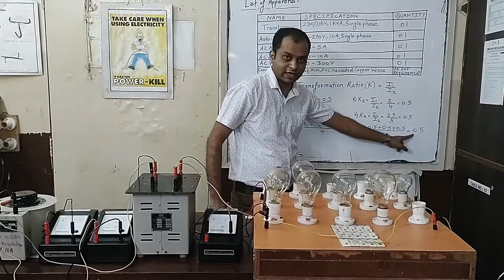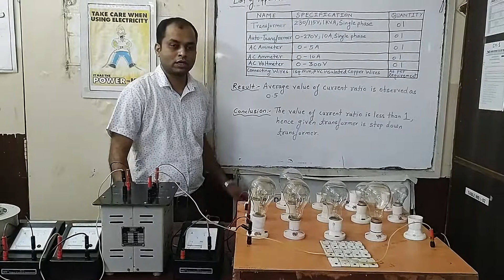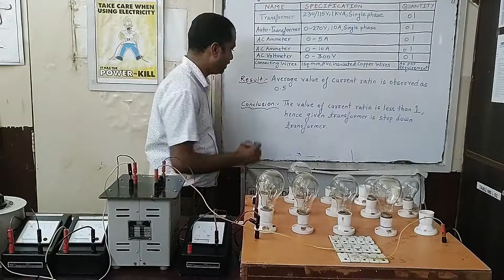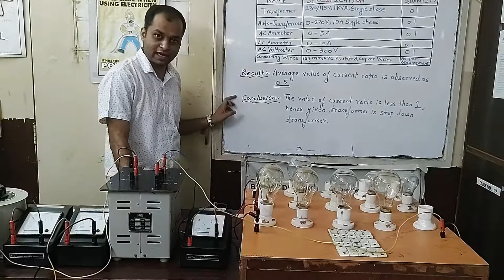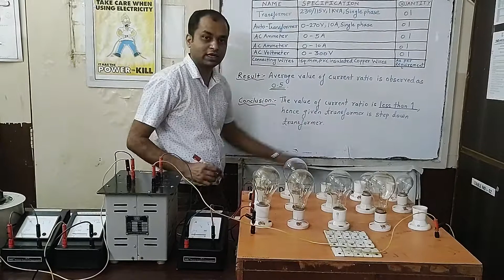After that, we have to calculate the average value of K, which is given by adding all 4 readings and dividing by 4. Doing this calculation, the average value of K that we get is equal to 0.5. So after the calculation, in the result we have to write that the average value of the current ratio for the given transformer is observed to be equal to 0.5. From this we can derive the conclusion that, as the value of the current ratio for the given transformer is less than 1, the given transformer is a step down transformer.